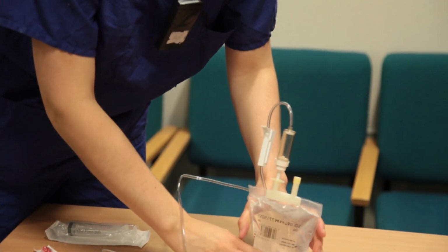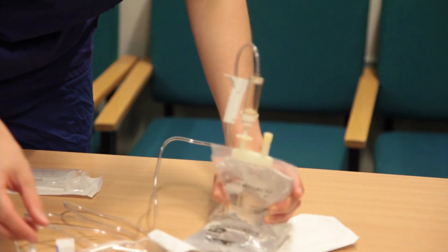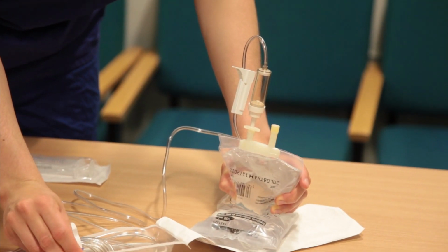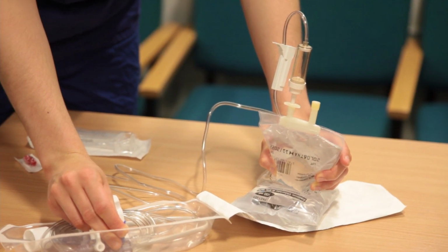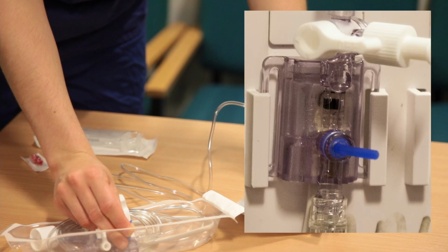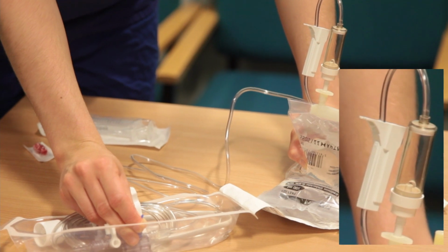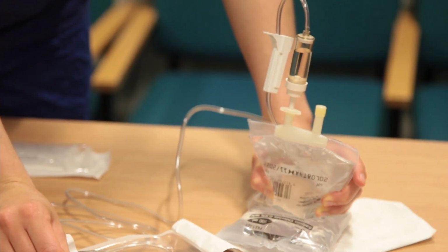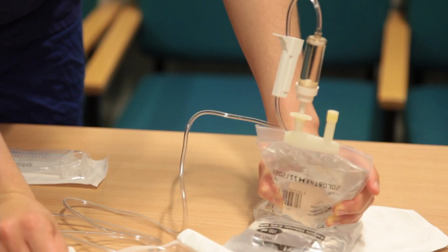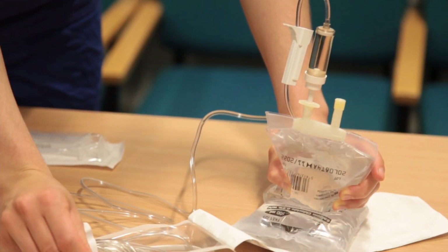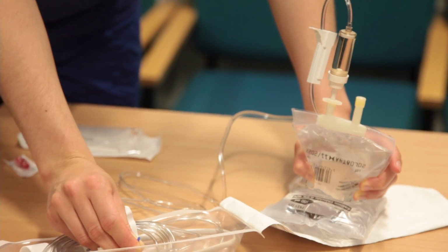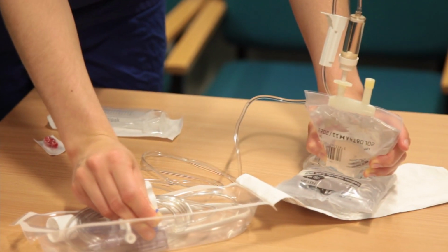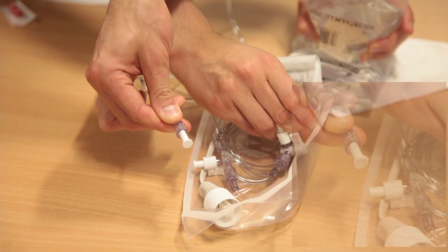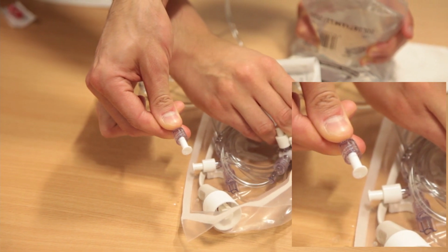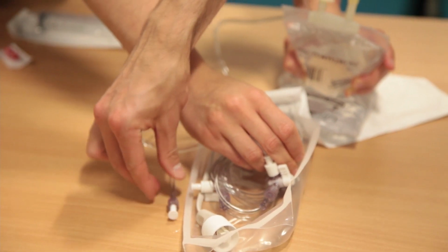Then, holding the bag upside down, apply gentle pressure whilst pulling the blue rubber flush band on the transducer itself. This should allow the air chamber to gradually fill with saline, and continuing this manoeuvre until the whole chamber and giving set are filled with saline will allow a full prime of the set. When water is visible at the end, you know the full set has been primed.